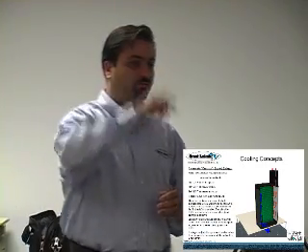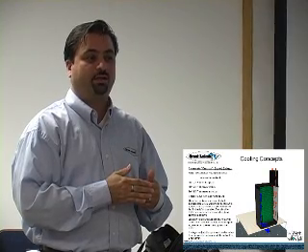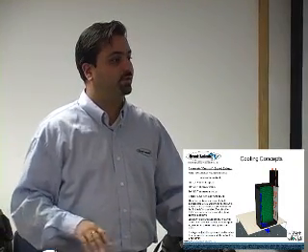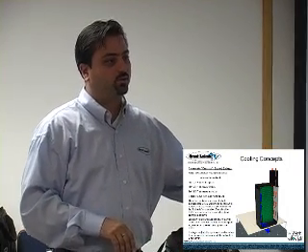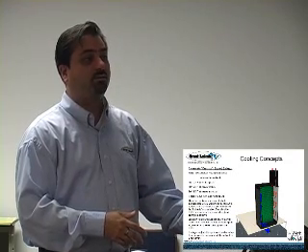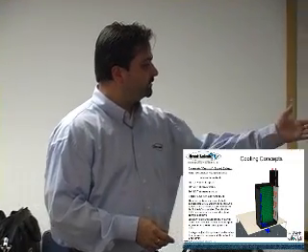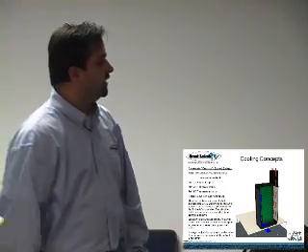On a cabinet far away, you may have to adjust your opening to maintain your pressure throughout your data center. So that's one thing that is critical: when you start cutting holes in the raised floor, you can adjust how many perf tiles you have. That works the same way as this adjustable ducting system, maintaining pressure.